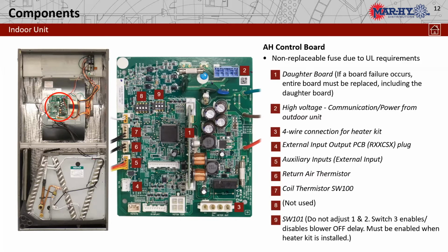be touched, but 3 will be enabled. You will switch that to on anytime you have a strip heat going in the unit. What that does, it sets the delay fan off timer, so we can get fan operation on shutdown to make sure we take all the residual heat off of the heat elements. So I would suggest on any installation, regardless of strip heat or not, enable switch number 3, switch it to on. That will be a safety thing we do not want to have to deal with later. So every install, switch dip switch 3 to the on position.